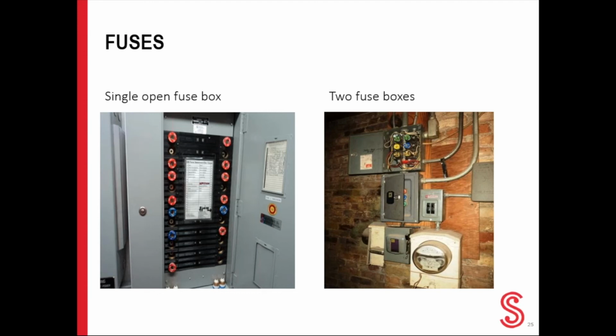And of course, what they consist of is a metal strip or a wire element, which is mounted between a pair of electrical terminals, and then it's enclosed by a non-combustible housing such as ceramic or glass. For the most part, fuses were replaced by circuit breakers in the late 1950s because they're not designed to deal with the increased electrical loads of modern living in regards to electrical and technology advancements of today. So how do they work, you say? When an electrical current, which is too large for a fuse to handle, comes through the fuse, the wire element itself will melt and break and stop the flow of electricity.